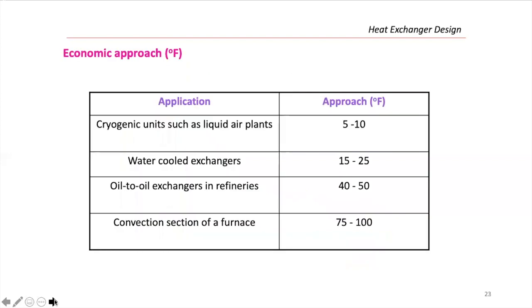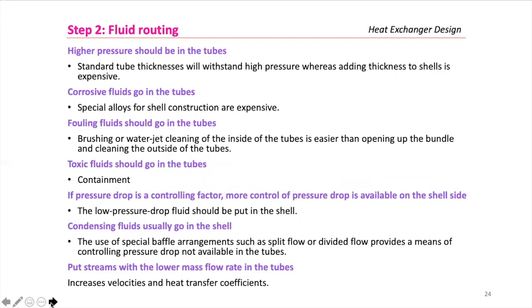Economical approach temperatures vary by application. For cryogenic units such as liquid air plants: 5–10°F. Water-cooled heat exchangers: 15–25°F. Oil-to-oil heat exchangers: 40–50°F. Convection section of a furnace: 75–100°F. Once you calculate your approach, verify it is within the economic range for your application. Step two is selecting which fluid goes through the shell and which goes through the tubes.